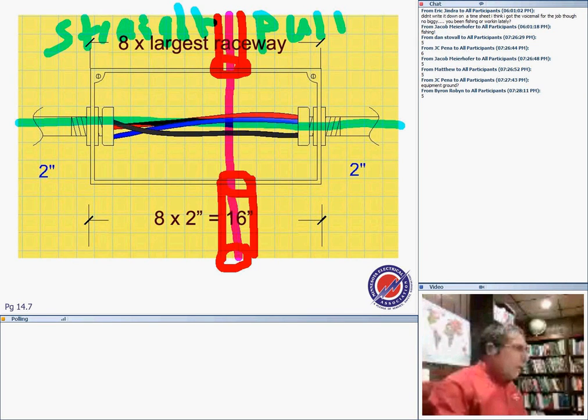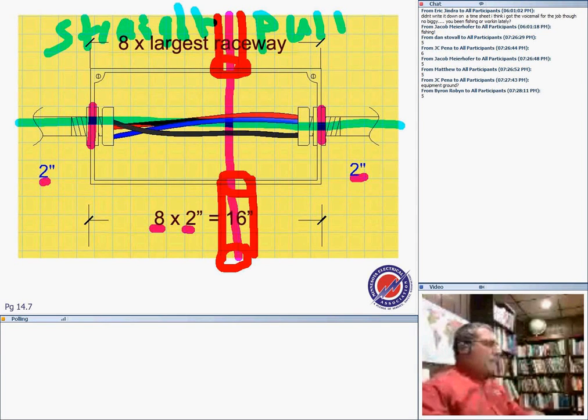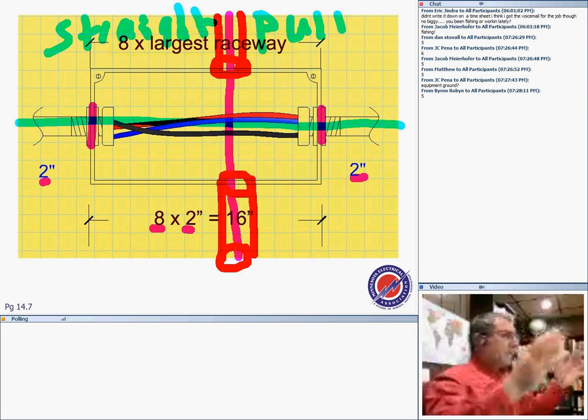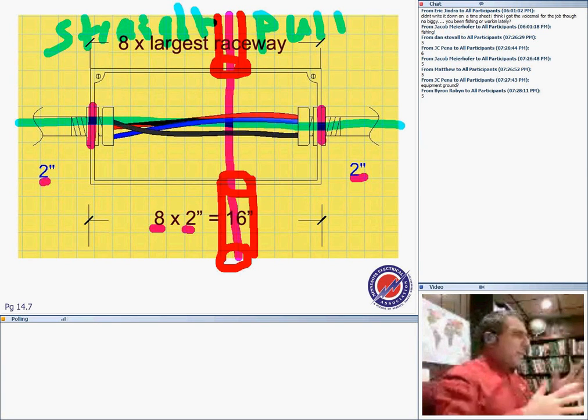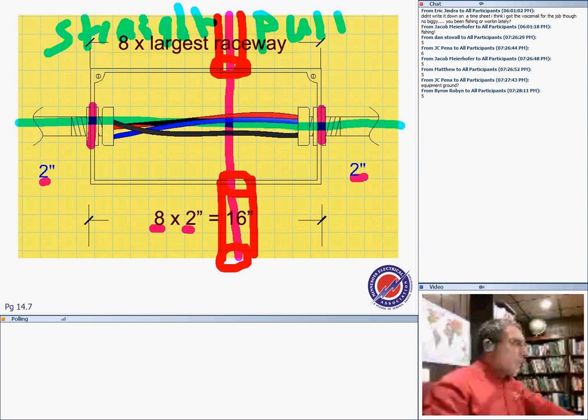Alright? Okay, now, when you have a straight pull, guys, you can find the distance from where the conduits enter to where the conduits leave. The largest conduit engaged is 2, so the width of the box is 16. Any questions about how they came up with 16? Why 8? Because the code says, for a straight pull, you take the largest conduit engaged in the straight pull, multiply it by 8, and that will be the width of this box.